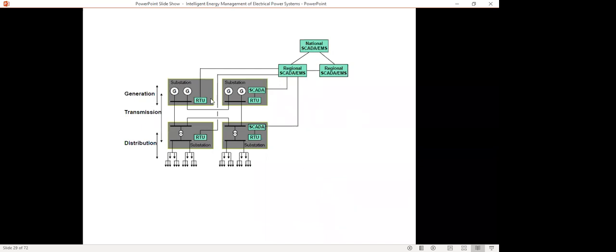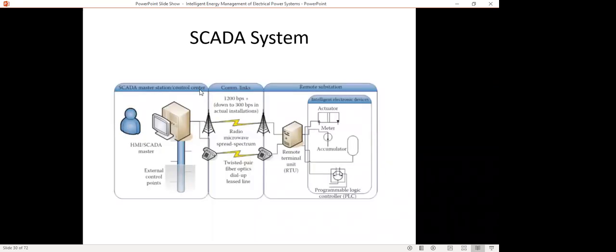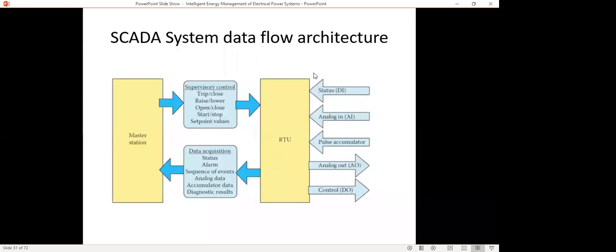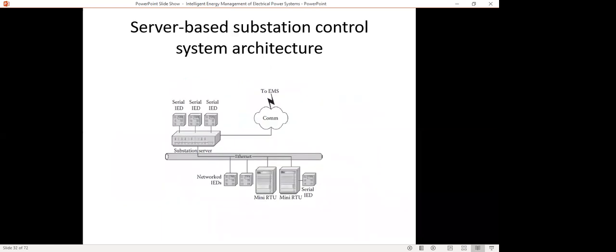So here, the data we are collecting from the substations through the remote terminal units is transmitted to the regional center, the regional SCADA energy management system center. From that, it can be sent to the national SCADA energy management center. So the SCADA system collects the information through the RTU and transmits it to the SCADA master station. From there, it receives the control signals. Based on the control signals, it actuates. So this is the picture, the SCADA system data flow architecture.